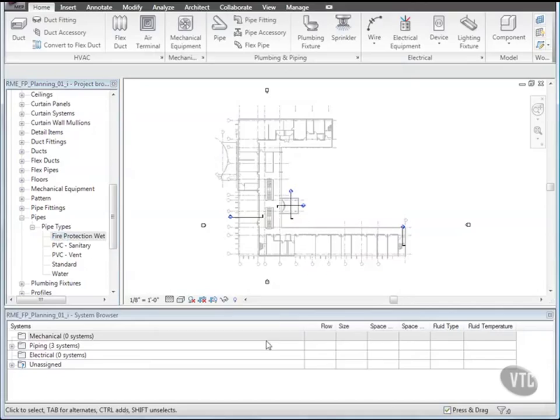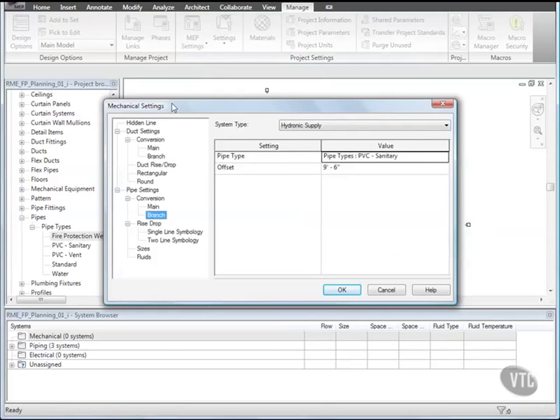Next, we'll configure Pipe Conversion Settings. Click the Manage tab, and from the Project Settings panel, click the MEP Settings drop-down and select Mechanical Settings. In the Mechanical Settings dialog, on the left side under Pipe Settings, select Conversion, then Main, and from System Type, select Fire Protection Wet.